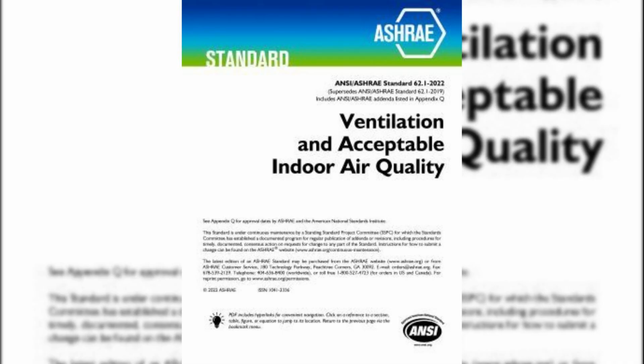Codes and standards you need to know. ASHRAE 62.2, Residential Ventilation. ASHRAE 62.2 is a minimum national standard that provides methods for achieving acceptable indoor air quality in typical residences. It was developed and is maintained by the American Society of Heating and Air Conditioning Engineers. ASHRAE sets the whole house required ventilation rate. The common form is roughly area plus people. The whole house ventilation rate is often calculated using the following formula: 0.01 × square footage + 7.5 × (number of bedrooms + 1). Whole house ventilation means exhausting stale indoor air and replacing it with fresh outdoor air.